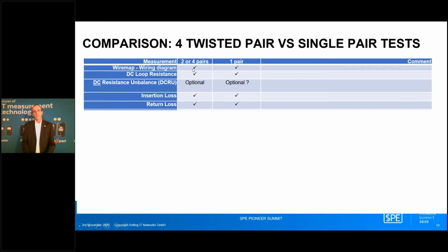That became important for 2 and 4 pair cabling, mostly for 4 pair Power over Ethernet applications that go up to 90 watts, because cables in that high power range can become substantially warmed. So the loop resistance measurement wasn't good enough anymore. You need to take care of single wire resistance. On 1 pair cabling, it is more difficult. If you have an unshielded cable that's 1 kilometer long, for example, or it just doesn't end at the same location, you can't do a single wire measurement anymore. So there are discussions whether that parameter is actually doable in the field, and how we should measure it in the field.